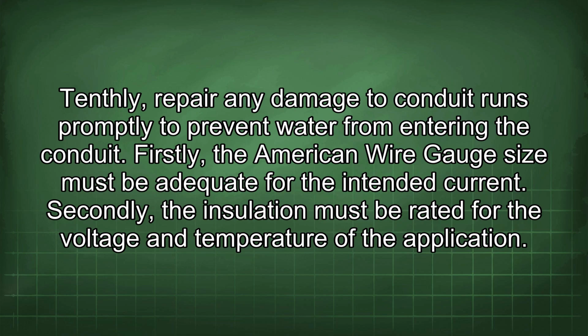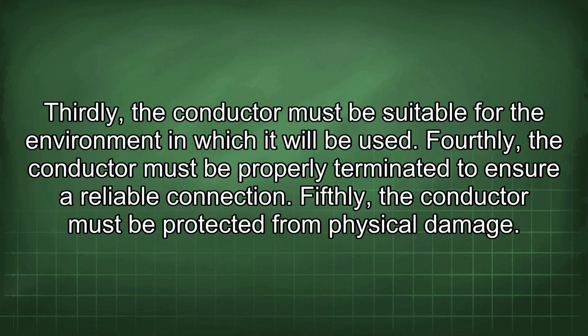Firstly, the American wire gauge size must be adequate for the intended current. Secondly, the insulation must be rated for the voltage and temperature of the application. Thirdly, the conductor must be suitable for the environment in which it will be used. Fourthly, the conductor must be properly terminated to ensure a reliable connection.